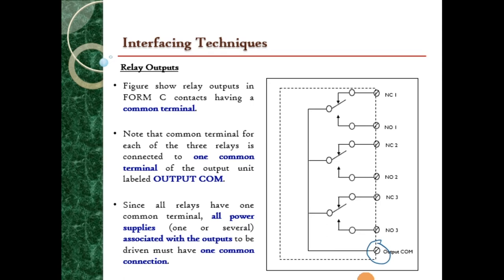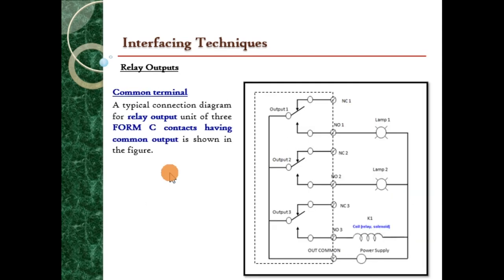Since all relays have one common terminal, all power supplies associated with the outputs to be driven must have one common connection. So meaning that, let's say this is output 1, output 2, and output 3, each of these outputs must have a common input to the output COM. This is an example of the common terminal using Form C contacts. For example, the first output is illuminating lamp 1, the second output is lighting lamp 2, and the third output is energizing a solenoid here. So all of the outputs are connected to the common power supply here. This is the common terminal of the relay outputs.